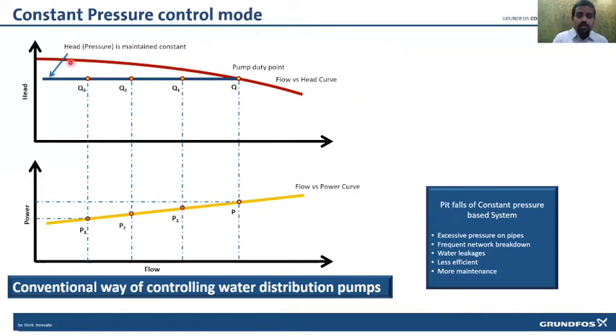Just briefing through a pump curve. For example, we all know the pump curve, where the x-axis is the flow and the y-axis is head. And this is a duty curve point, the flow and head, the peak flow. For the peak flow, the head which we have arrived at is, say, 80 meters. But when the consumption reduces, the friction loss also reduces, but we are not reducing the set point. We maintain a constant set point for variable flow, which is not required. So what happens is when we do that, we put more pressure on the pipe, we consume more power, and we send out more water for the consumption.